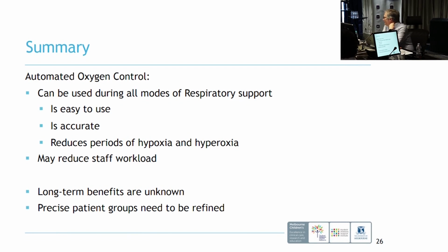Normally the signal should stop. The signal stops, and after a while, it turns off. It continuously monitors the signal quality. If the signal quality drops, it alarms. Then you will have the alarms, and the ventilator keeps the last FiO2 that was set. It can go up quite high quickly, but it alarms. It shouldn't change.